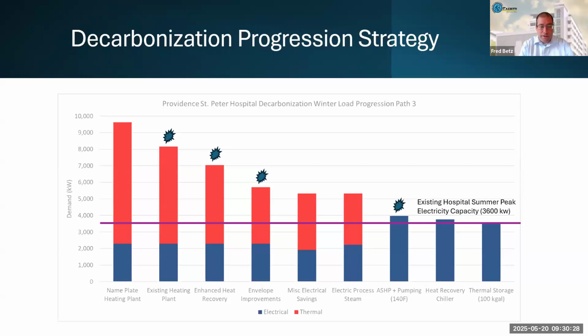Another thing I'm finding with a lot of facilities that I work on, there's a lot of old envelopes. So ordinarily, this is another one of those myths, when you say, oh, we need to improve the envelope. From an energy performance perspective, especially when you're doing a newer facility, making envelope improvements is very minor incremental. The envelope has been regulated for a long time. But if you go to much older facilities, so for example, about half of this hospital is pre-energy code, you'll find a lot of windows with a U value of 1 and uninsulated walls with an R value of 2 or 3.